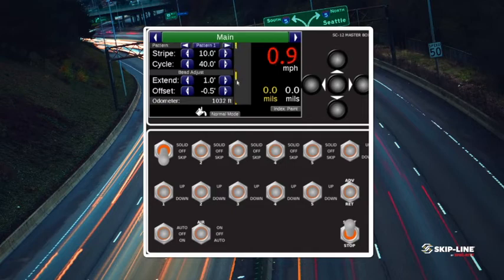like the start of the skip, and the distance to the next beginning of skip. So the beginning of one skip to the beginning of the next skip. That will tell you if your motion sensor is in calibration. So it doesn't really matter what the stripe length is. Maybe this stripe is 25 foot long and this one's 15 foot long. I mean, most people just jump to the conclusion that this is a motion sensor issue. Not necessarily. That is why you need to measure the distance between the beginning of one skip and the beginning of the next, regardless of the stripe length. If that is accurate, then you do not have a motion sensor issue.